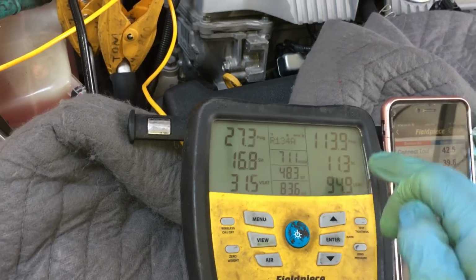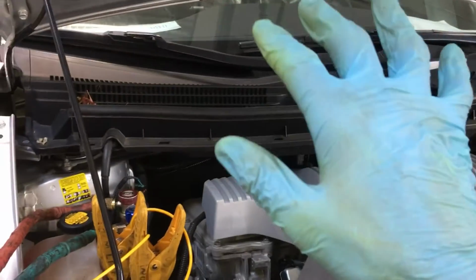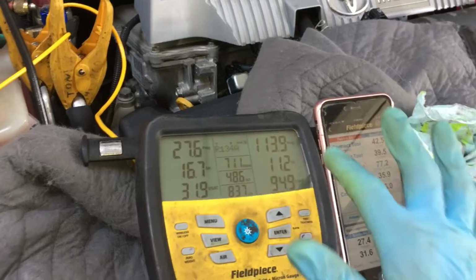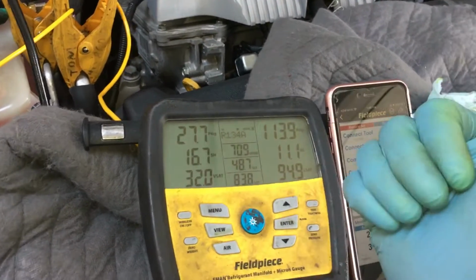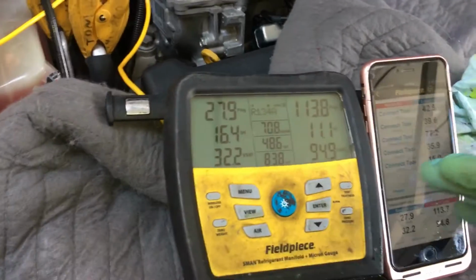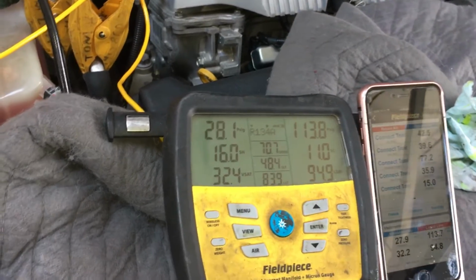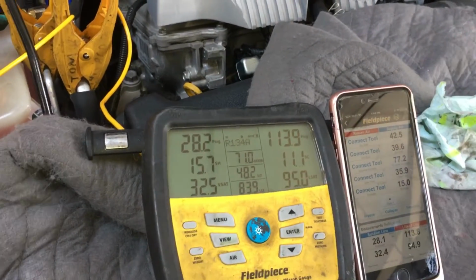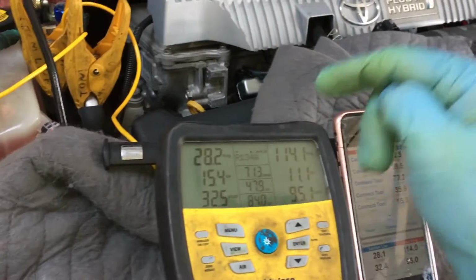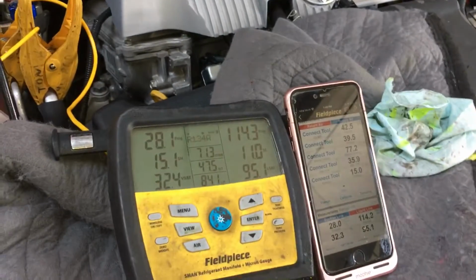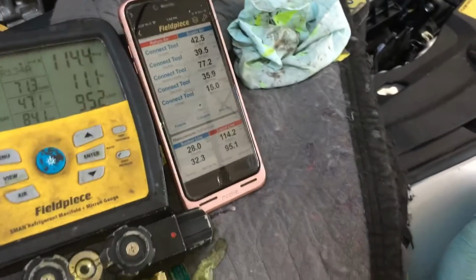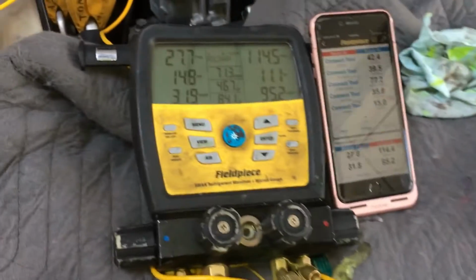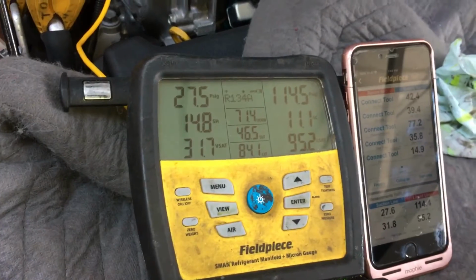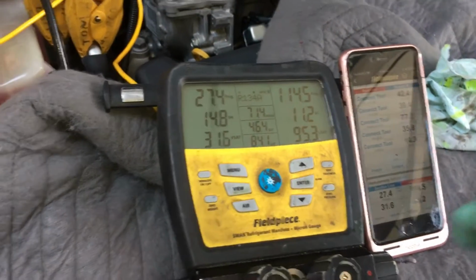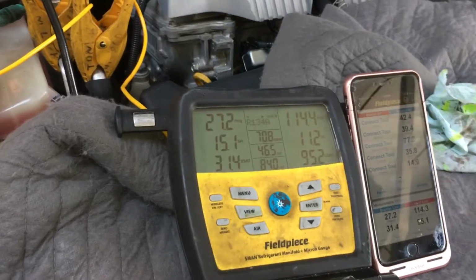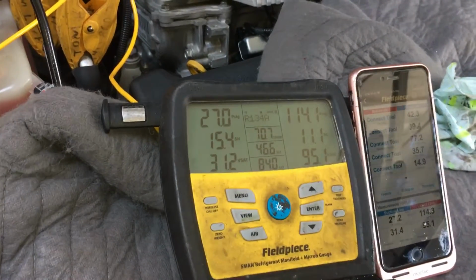Now, at the beginning, at the ambient temperature with no sun load, at this low ambient temperature, I wouldn't have expected to see, like I seen, 160 psi on the high side. Even with it winding out, I would not normally have seen that high of a high side with the system calling for full cold under these ambient conditions, under normal conditions. But because this is an aftermarket condenser that is less than the capacity of the OEM, it had to work harder, and with the compressor winding, the high side pressure went up more than I would normally see.